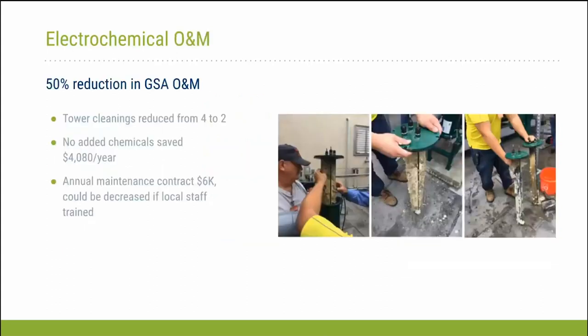Next slide. We also looked at the operations and maintenance costs. What we saw was roughly a 50% reduction in the O&M costs, and a lot of that had to do with tower cleanings. Normally at the site, they performed 4 tower cleanings where they had to spend a couple of guys and several man-hours to spray wash the cooling tower fill and reduce scale. The site was very involved in this, the maintenance people, and their estimation was that the cooling tower was cleaner after the system was installed. I think the scale was easier to remove, and they felt that the number of cleanings could drop from 4 to 2, so we included those O&M cost savings.